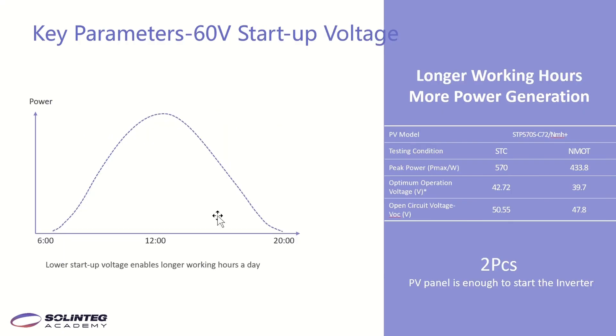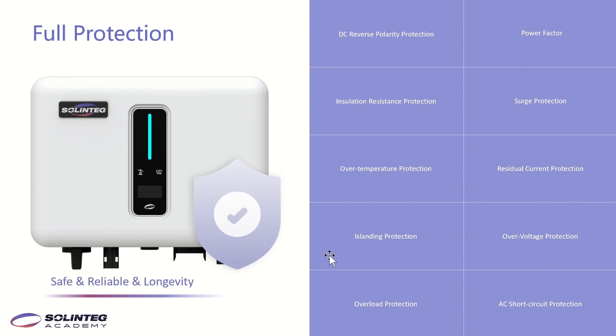This page shows the benefits of the 60V startup voltage. If the startup voltage is lower, PV panels start working earlier in the morning and stop later in the evening, enabling longer working hours per day. Generally, a PV panel's operating voltage is about 40V, so two panels in series are enough to start the inverter. There are also many protections integrated in the inverter, including DC reverse polarity protection, over-temperature, overload, over-voltage, and short-circuit protection — ensuring safe operation and long reliable lifetime.